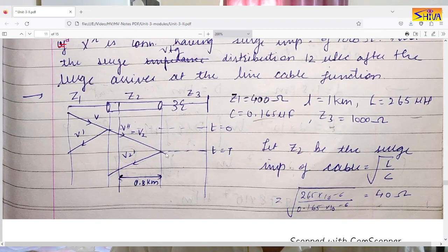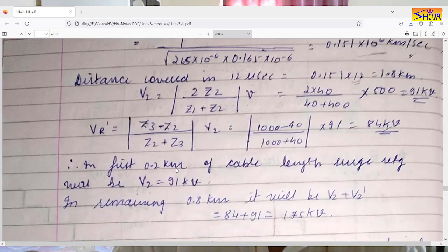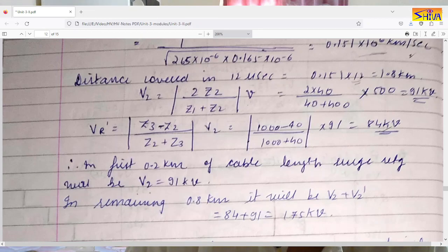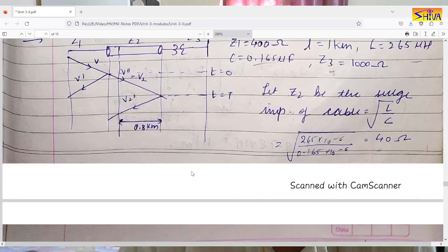The transmitted voltage V2 = 2Z2/(Z1 + Z2) × V = 91 kV. The reflected voltage at the transformer end is V2' = (Z3 − Z2)/(Z2 + Z3) × V2 = 84 kV. So in the first 0.2 km of cable the surge voltage is only 91 kV, while in the remaining 800 meters it is V2 + V2' = 91 + 84 = 175 kV. This is the surge voltage distribution in the cable after 12 microseconds.